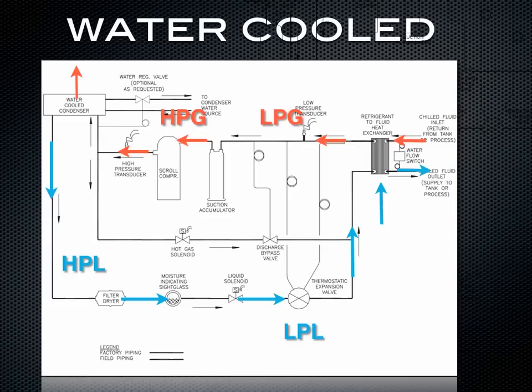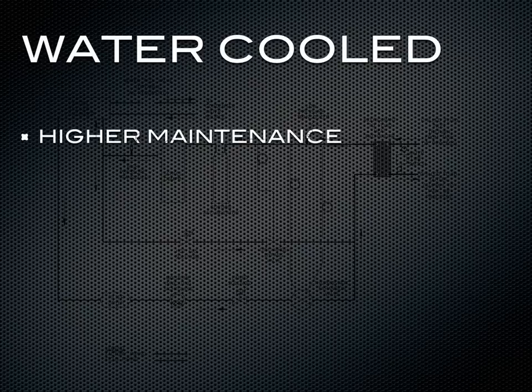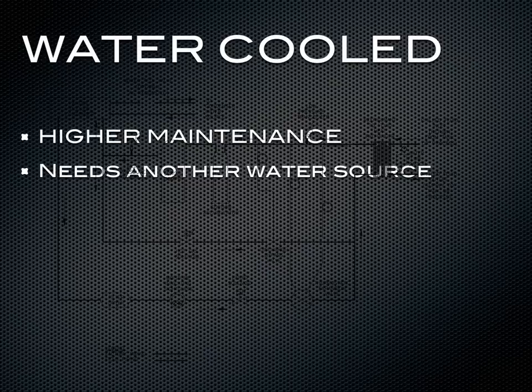I want to go over a couple quick things about water-cooled chillers you might want to know. There is higher maintenance on the condenser side of a water-cooled chiller if you have a cooling tower. A cooling tower needs treatments and chemicals, and there's the labor that goes into that, and that cost will add over time. As stated before, you need to have another water source for the heat to be rejected to, so these water-cooled chillers do not stand alone like an air-cooled chiller.